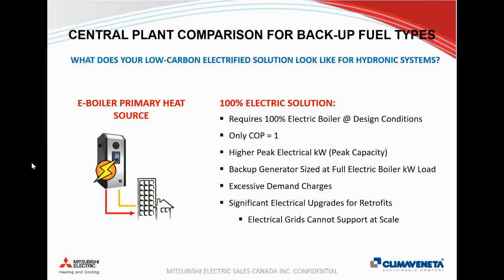But I think there's drawbacks to that. A lot of buildings won't have enough capacity to do that in the first place, so you might need to upgrade your service. You're fixed now to a COP of 1. You're going to have much higher peak electrical demand charges by having that inrush current every time the boiler turns on. And if your project requires a backup generator for the heat source, then now you need to oversize your generator to have enough power to produce electricity to run an electric boiler at a COP of 1.